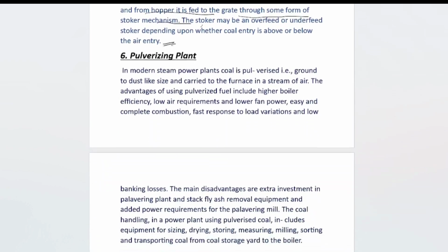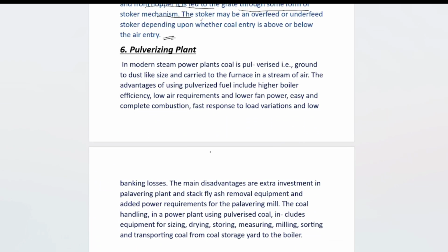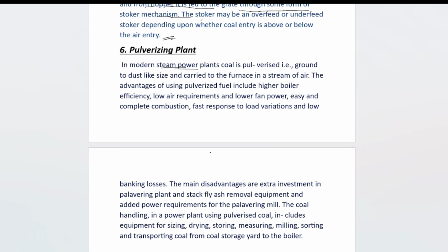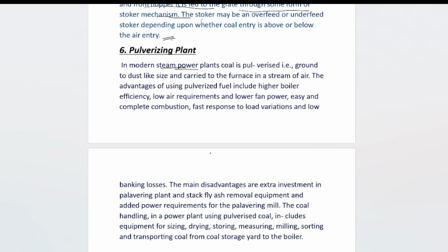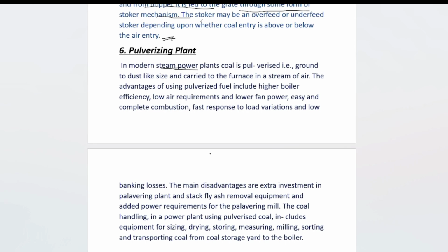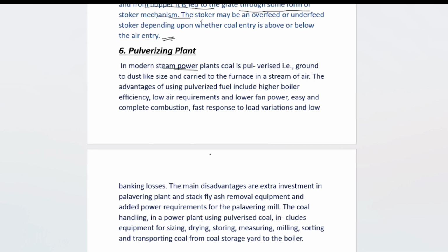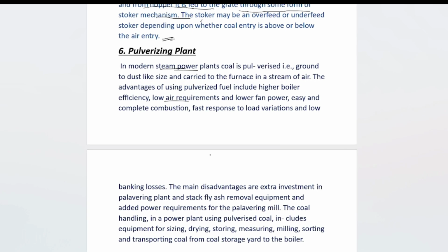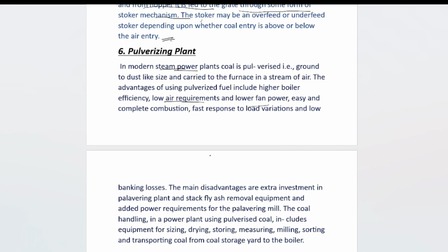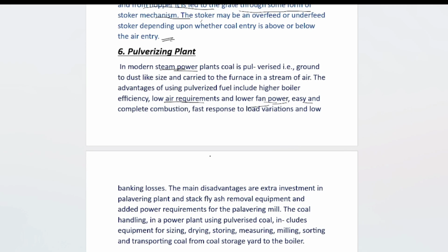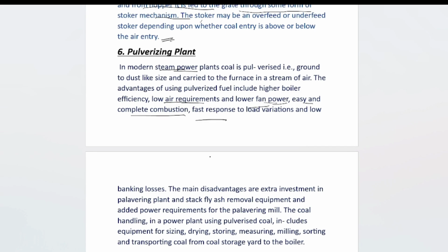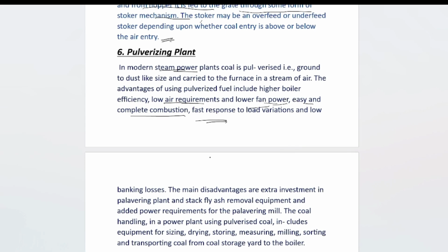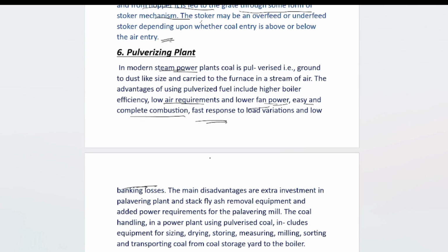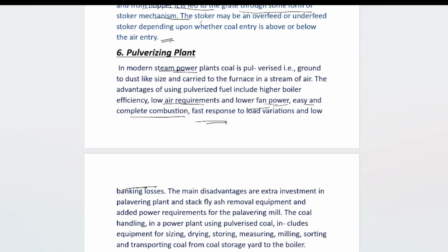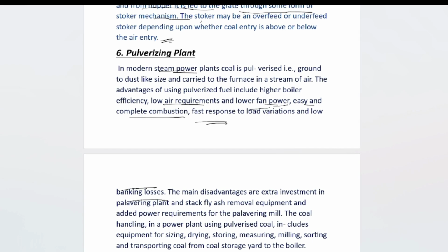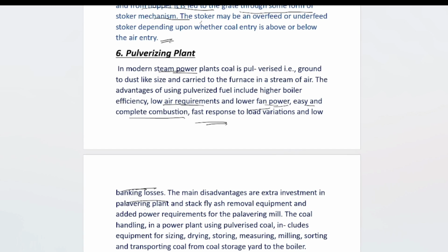Sixth section is the pulverizing plant. In a modern steam power plant, coal is pulverized, ground to a dust-like size and carried to the furnace in a stream of air. The advantages of using pulverized fuel include higher boiler efficiency, low air requirements, lower fan power, easy and complete combustion, fast response to load variation and low banking losses. The main disadvantages are the extra investment in the pulverizing plant and in ash removal equipment, and the added power requirement of the pulverizing mill.